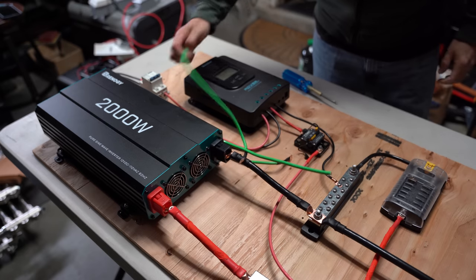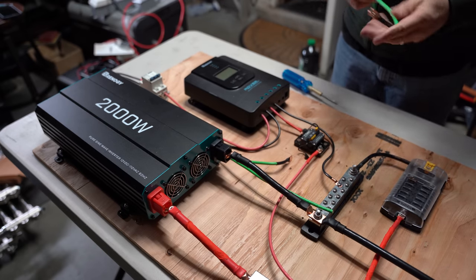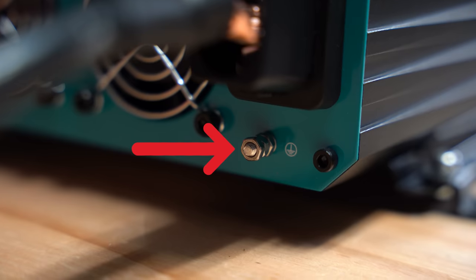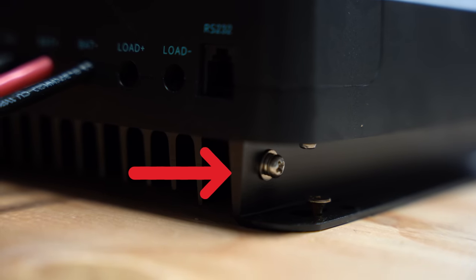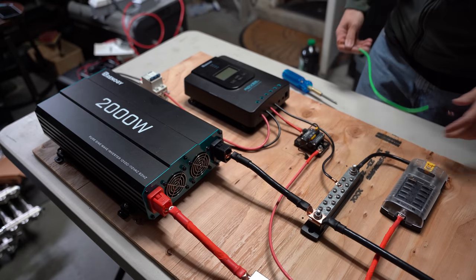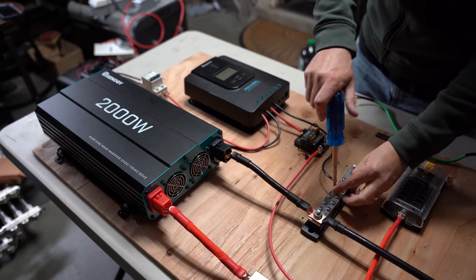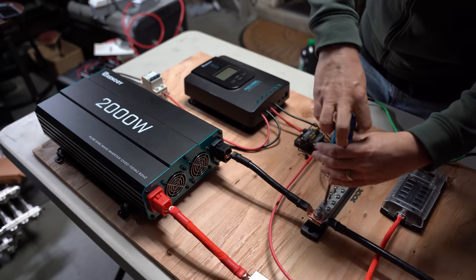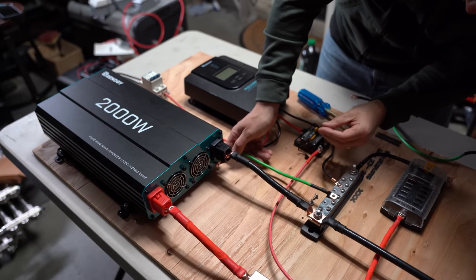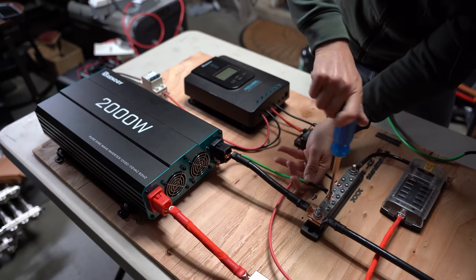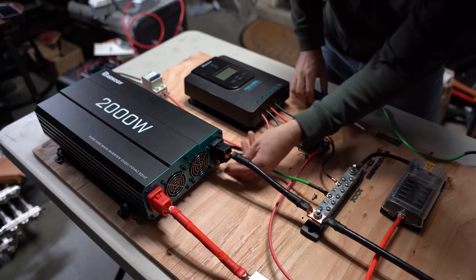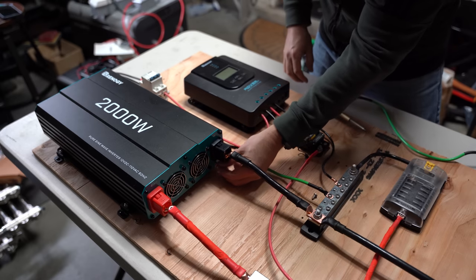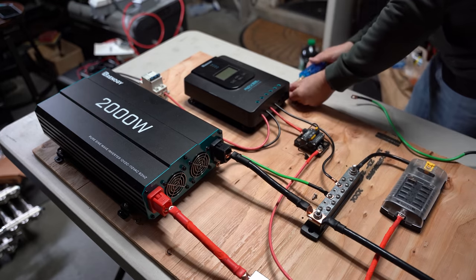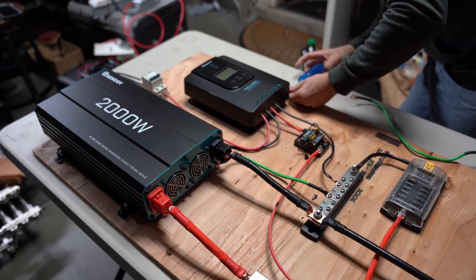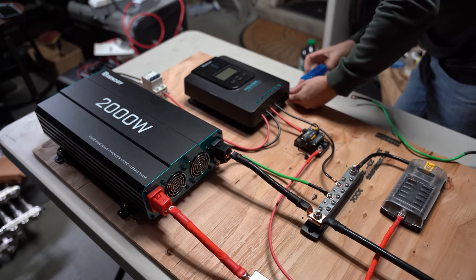Grounding. Next, we need to ground our inverter and charge controller. If you look at the side of both of these, they have a grounding connection that we can connect to. Depending on where you put this setup, for example, if you're in a vehicle, you want to connect the grounding cable to the chassis. I'm going to be putting my setup in a shed in my backyard, and I have a grounding rod that I can connect to there. You can also connect these to the negative bus bar in your system as shown here, and then connect the negative bus bar to the grounding device. I'm using a green 6-gauge wire. Green is typically the color for grounding.